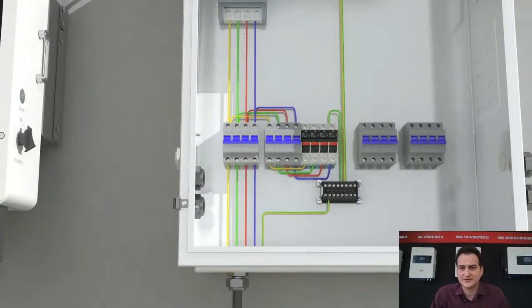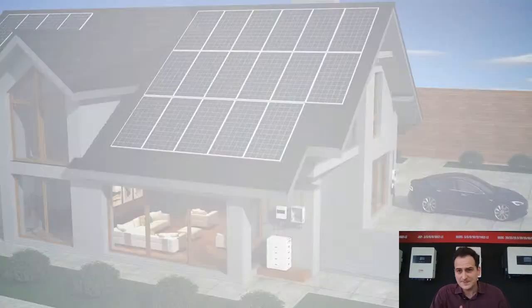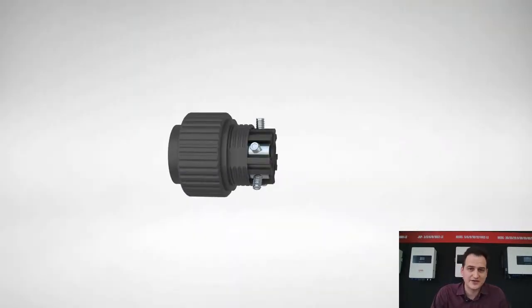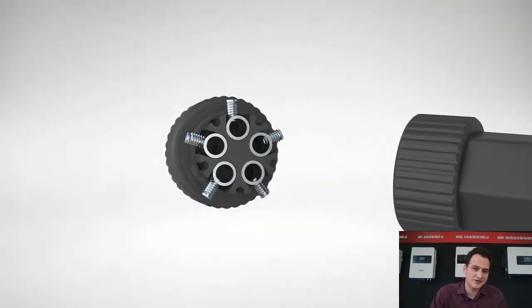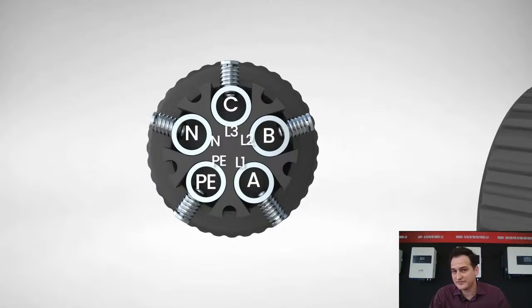And here we have the AC board. So the circuit breaker we recommend is at least 32 amps. We have the 5 kilowatt unbalanced output. So minimum, it can be around 26 amps, 27 maximum. So 32 is the minimum circuit breaker for our inverters to work correctly. And then the GEN connection. For the GEN connection, same way. So we're wiring the connector and then putting it into the inverter.